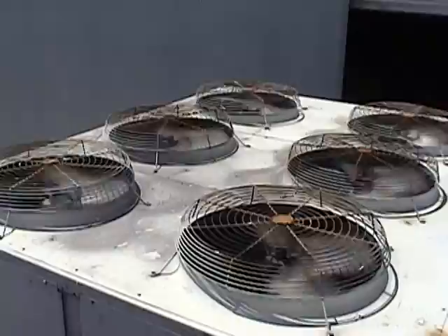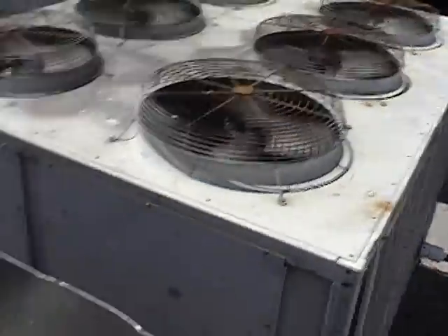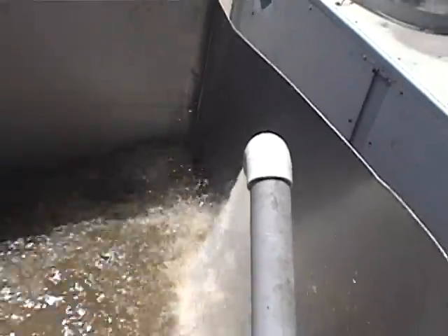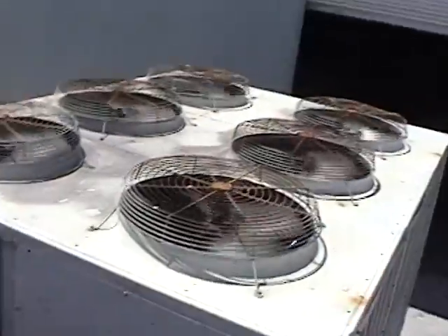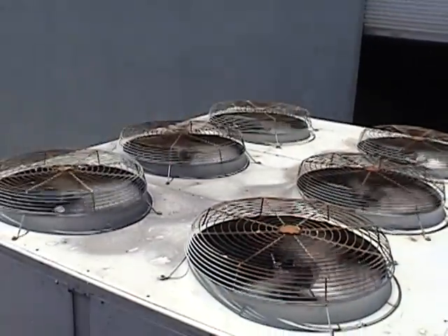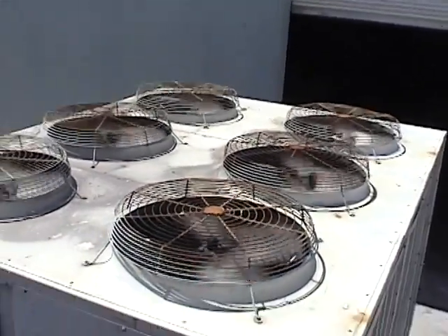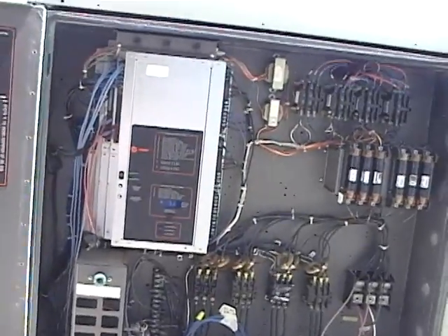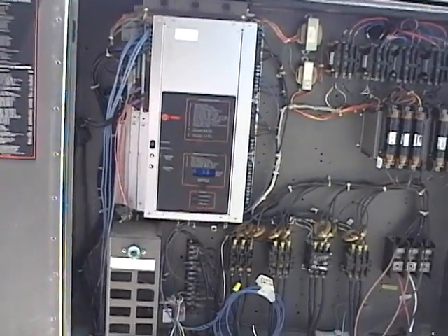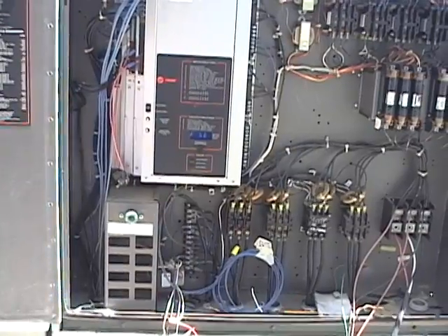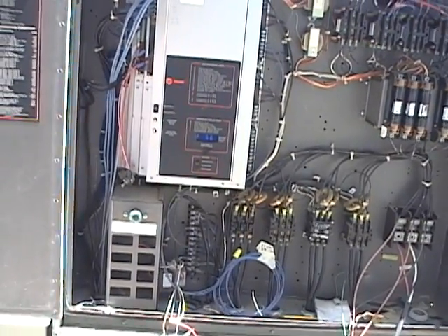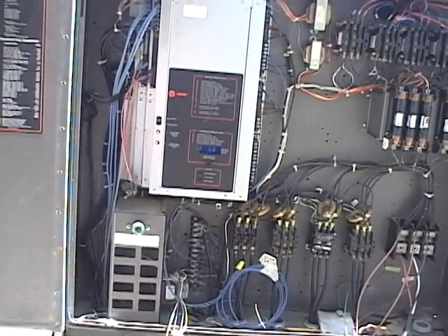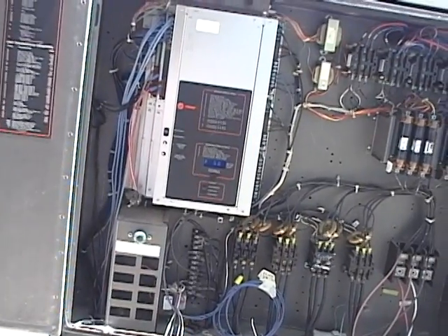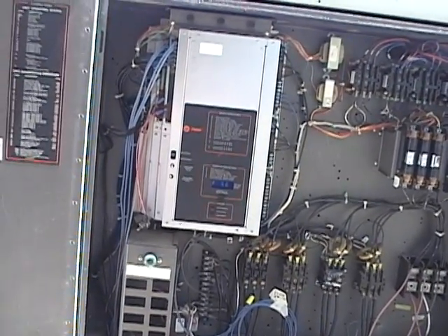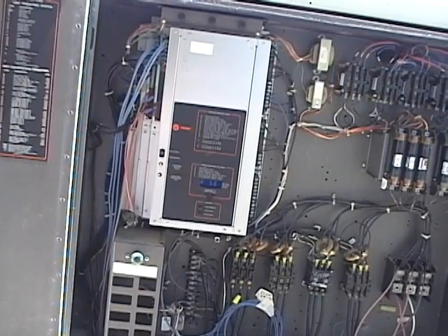He's pulling well. Here's our water returning to our holding tank. The chiller, as it is, is very quiet. You'll notice now that the leaving temperature is now 56 degrees. So in a few minutes we'll start to hear the chillers. The compressors will actually cut out because it'll say, okay, we've reached our set point, which is 55 degrees.